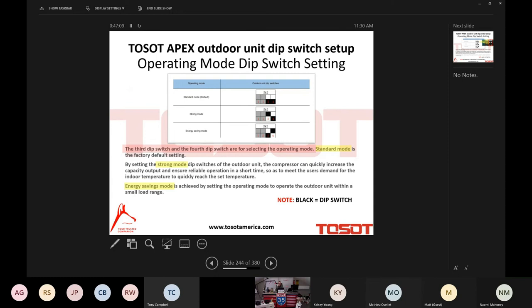Okay, the last 2 dip switches on the outdoor unit, 3 and 4, we are going to set the operating mode. 3 modes to choose from. Standard mode, that's the factory default. Strong mode. Strong mode is best described, my friends, in that it will bring the running frequency, the RPM of the inverter compressor, up to a higher frequency, up to a higher RPM quicker than it would in the standard mode. If we want the system to react quicker, right, we can do that by enabling the strong mode.